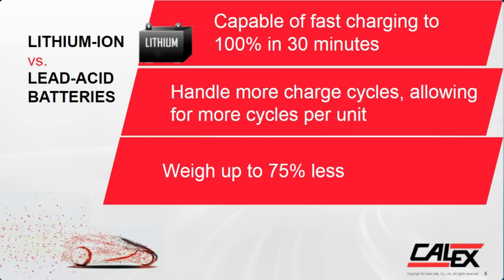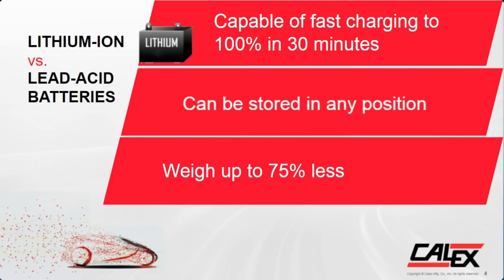Another big one: there's no need to store lithium-ion batteries upright like a traditional lead-acid battery. Even though lead-acid batteries are labeled as sealed, they still have to be stored upright because there is a vent system in them, whereas lithium-ion batteries are truly sealed. So you can take advantage of any dead space to fit the battery, such as marine applications or RVs. It's another advantage over lead-acid.